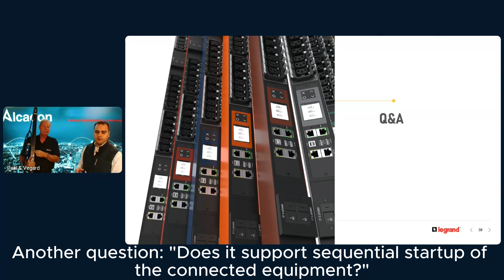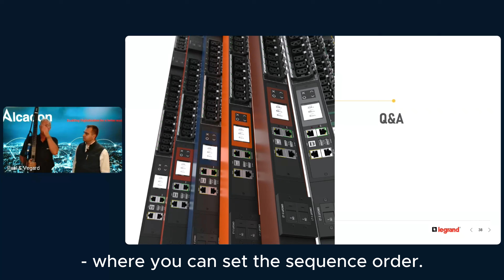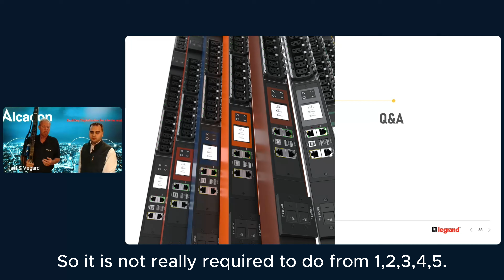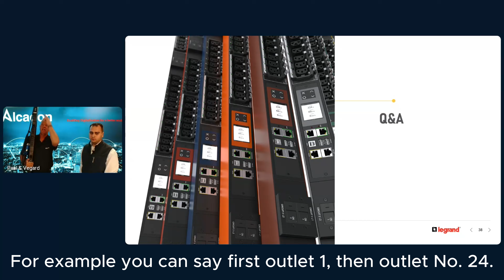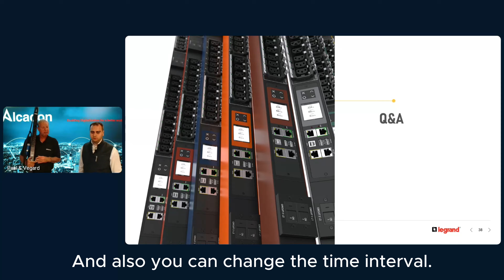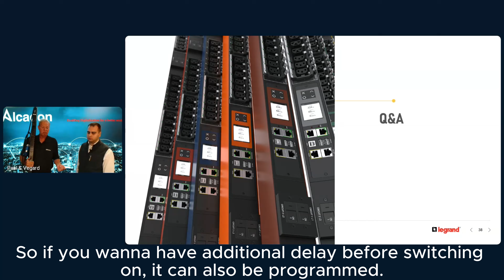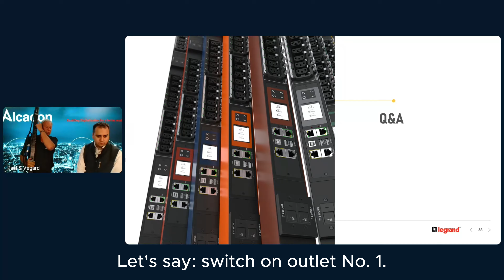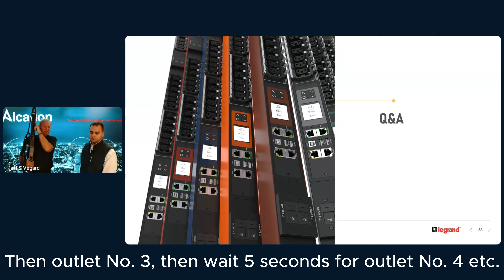Another question: does it support sequential startup of connected equipment? Yes, outlet-switched PDUs have this feature built in by default, where you can set the sequence order - it doesn't have to go 1, 2, 3, 4, 5. For example, you can say switch on outlet 1, then outlet 24. You can also change the time interval, adding delay before switching on - for instance, switch outlet 1, then outlet 2, wait 3 seconds, then outlet 3, then wait 5 seconds for outlet 4, and so on.